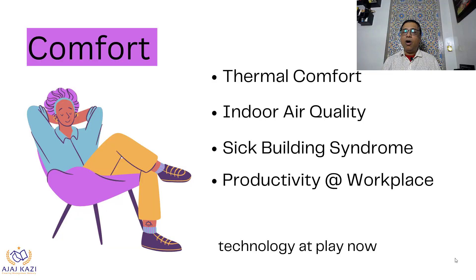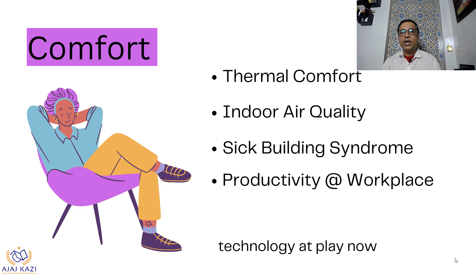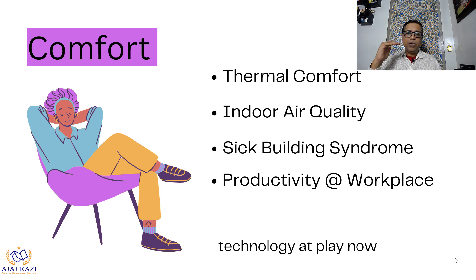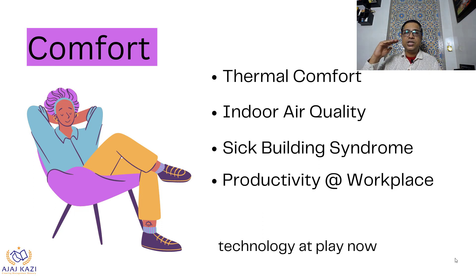Out of the four C's, the first C is comfort — specifically thermal comfort. Today in India there is a heat wave everywhere, and in certain places there are also heavy rains and snowfalls. When we look at thermal comfort for human beings, it has a certain temperature and relative humidity. Generally, 24 degrees centigrade plus or minus 1, and around 60% RH is the comfort level described by ASHRAE.